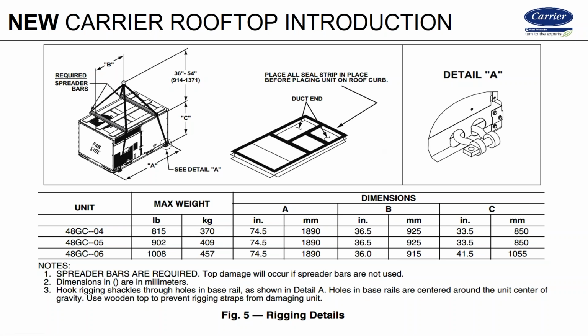If you've got pitched roofs, that's another thing you need to look at. We can get away with a little pitch, about an 1/8 inch pitch per foot from this side to that side, and still facilitate proper condensate drainage out of the rooftops. But if you've got any more than that much of a pitch, an 1/8 inch per foot, you need to look at a tapered or an adjustable roof curb. That way you can level the top out to the machine setting level. So always think about that when you're up on a roof and looking at things. Roof curbs can cause you a lot of headache.